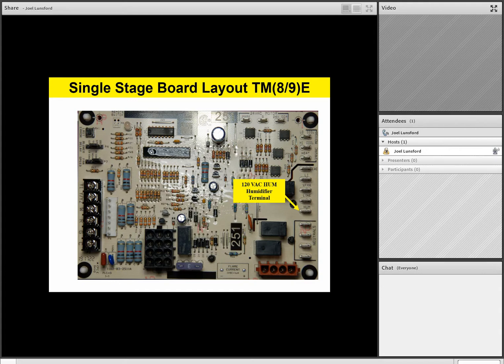So below that we have 120 volt neutral terminals. Again, all these neutral terminals are tied together, and if you were to look at this all wired into the furnace, that would be where all your white wires are hooked up. As we come around the bottom of the board, we have an output harness to the hot surface igniter and the inducer fan motor. Again, this is all harnessed in from the factory.